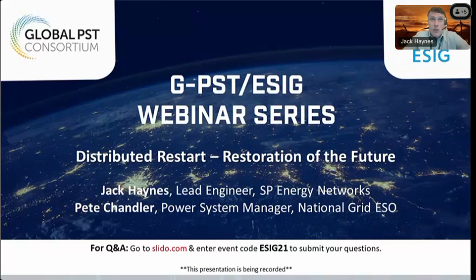When we turn the solar farm on, as part of the test network we not only had the solar farm, but there was a diesel generator there to support making sure we had sufficient state of charge for the duration of the trials. We did do 4-quadrant testing of the battery, pushing it through all 4 quadrants of P and Q output, so there were times it was charging both reactively and in terms of real power output. There'll be a section in the report about how the battery performed in the two control functionalities we used to do that. So yes, we did utilize it as a load.